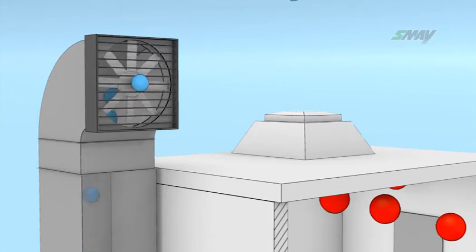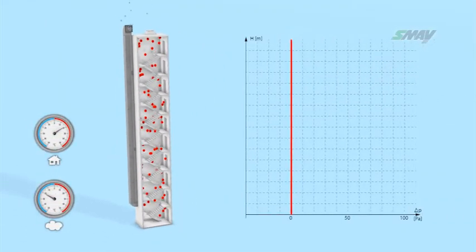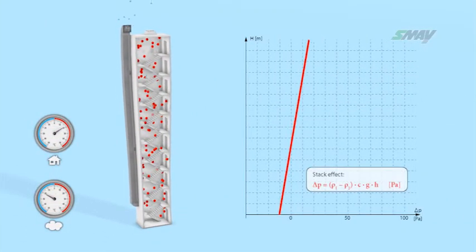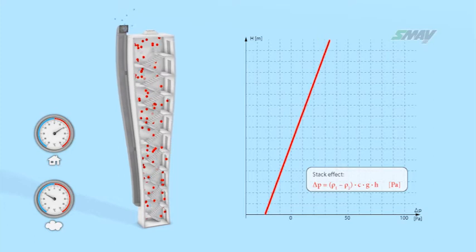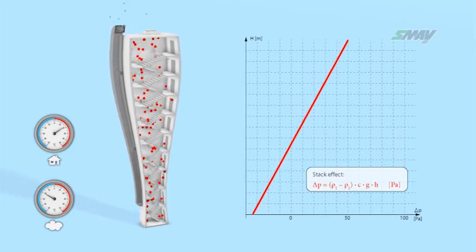However, if for that same system air is supplied to the stairwell at a temperature significantly below that of the inside, then a pressure gradient will occur as a result of the stack effect.